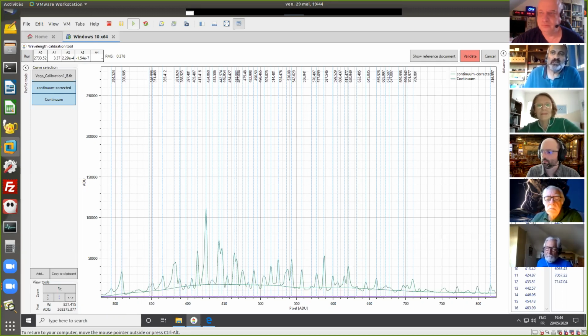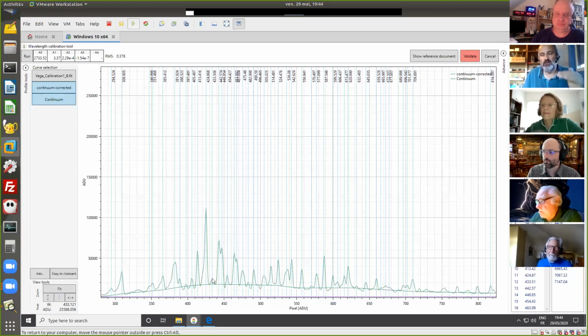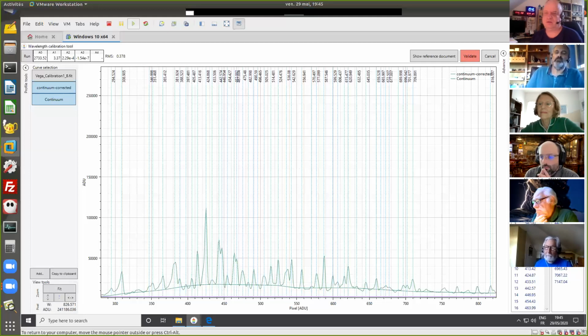And for each of them, we do a histogram of all the pixel values in this 80 pixel range. And we consider that half, so 50%, 0.5 here, the background rate, half of the pixels are in the background. So we consider in such a spectrum that the background is made of half of the pixels. Then, based on the 50% lowest values in these sections, we consider that we are in the background, and we measure the dispersion, so the RMS of the background itself. And then we multiply this value by, in this case, 7. So the threshold really comes from the image itself with the coefficient, while 7 sigmas means that we are far above the noise. Okay, I hope I answered the question.